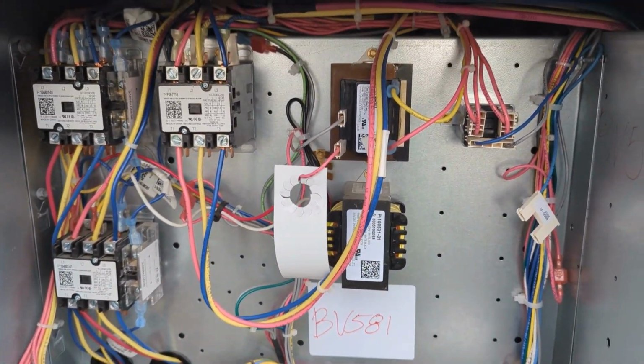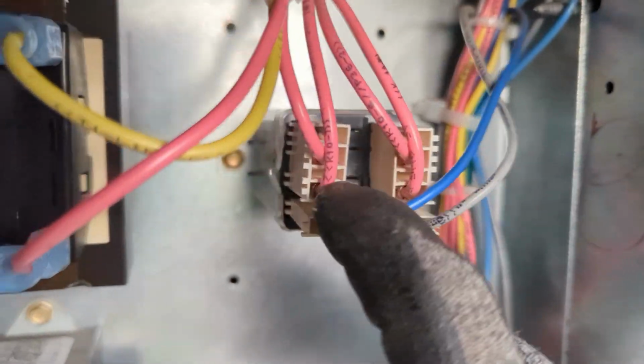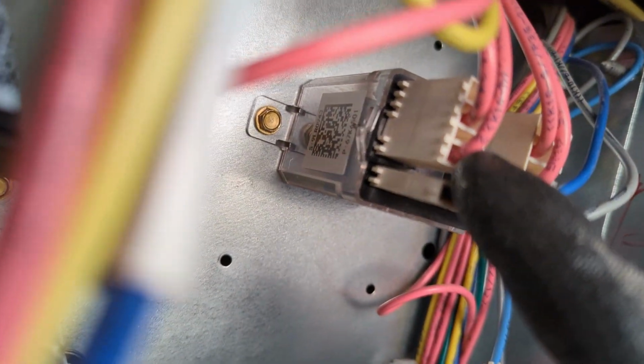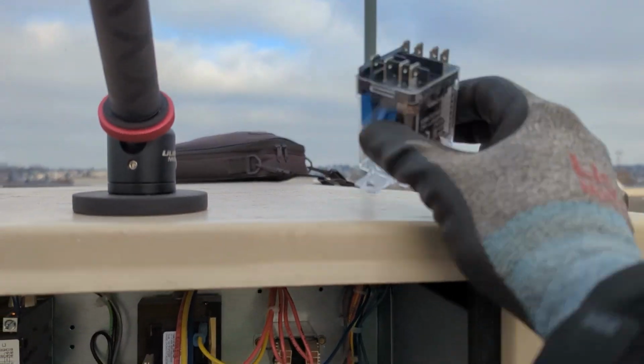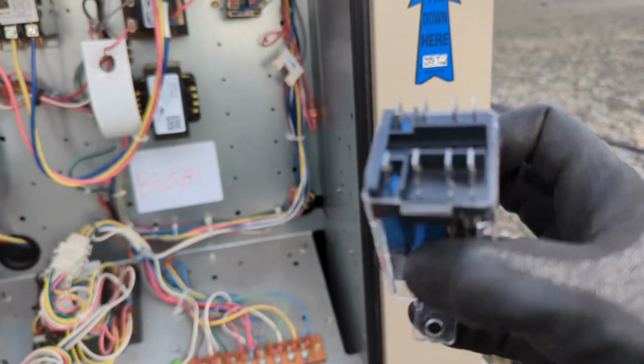We also replaced a fan relay, a condenser fan relay on a rooftop unit. We found this relay actually intermittently faulty a few weeks ago when we replaced the condenser fan motor. Unfortunately, it took this long to get this little relay - it's like this little cube, somebody called it an ice cube the other day. We just went onto the roof and replaced the relay. Pretty simple.